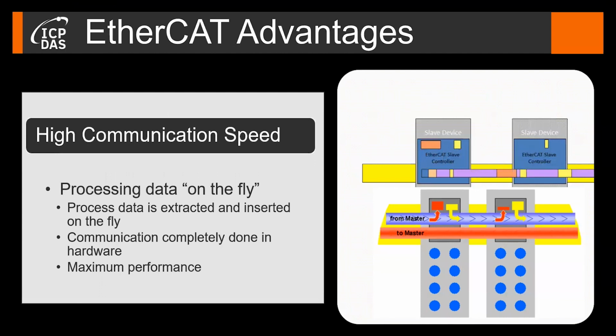What is EtherCAT? Why is EtherCAT so fast? What mechanism does EtherCAT use to achieve such a high communication speed? EtherCAT utilizes a processing on the fly approach for transporting data packages through each slave in the network. The main feature of this mechanism is that data exchange between the EtherCAT telegram and slave is completely done in hardware. So data extraction and insertion between frame and slave is done purely by hardware only.